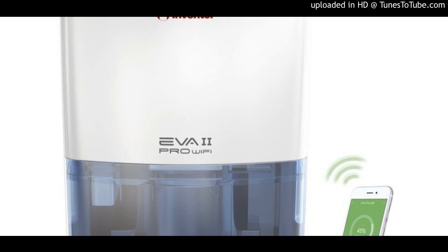2. Icing. After removing humidity from the air, the water can turn into ice if there are problems with the cooling system. Remove the front grille while the unit is operating, and if there is ice on the cooling system, it will likely need to be repaired.